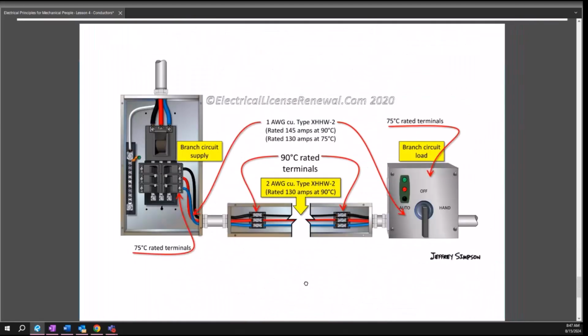All right, so the reason these columns are different is because conductors are rated at different temperatures based on what they melt at. So if they start melting at 75C, well, you can't push 90C worth of amps through them. It's not going to work because they will start melting. By the same token, if you have 90C conductor, but you have 75C terminations, the terminations will actually start melting. And I've seen that firsthand.